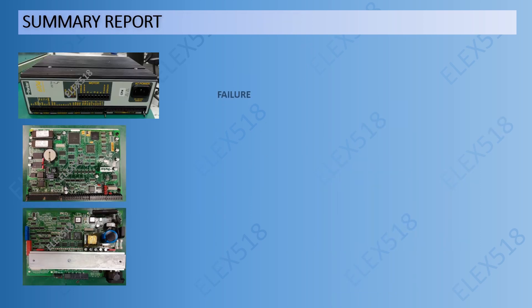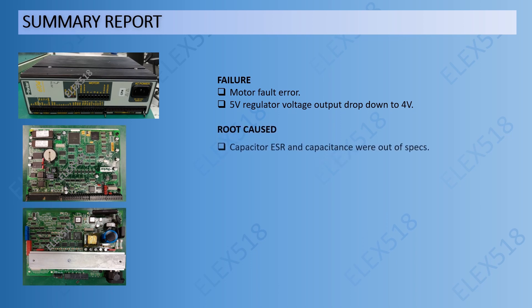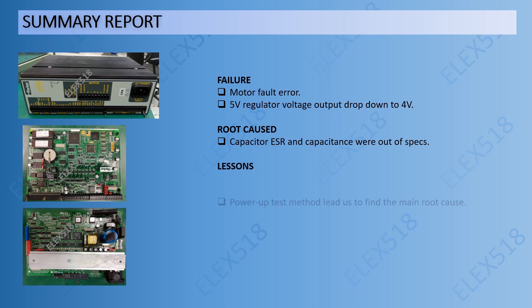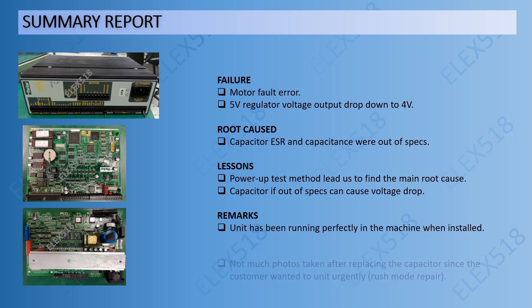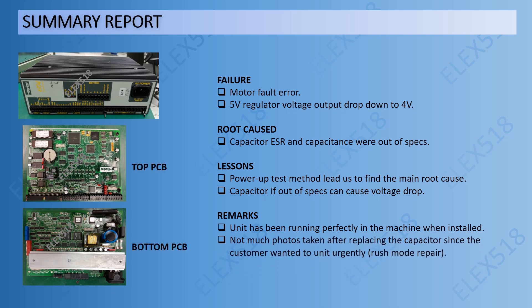Summary report. Failure: motor fault error — 5V regulator voltage output dropped down to 4V. Root cause: capacitor ESR and capacitance were out of specs. Lesson: the power-up test method led us to find the main root cause; a capacitor out of specs can cause a voltage drop. Remarks: the unit has been running perfectly in the machine when installed back. Not many photos were taken after replacing the capacitor since the customer needed the unit urgently, so it was a rush mode repair.